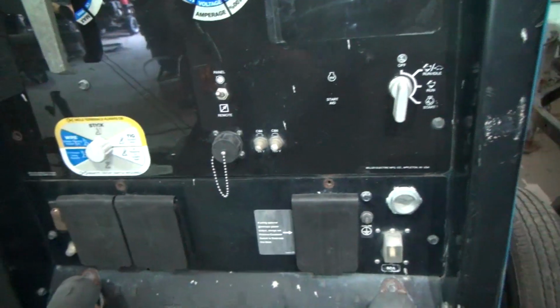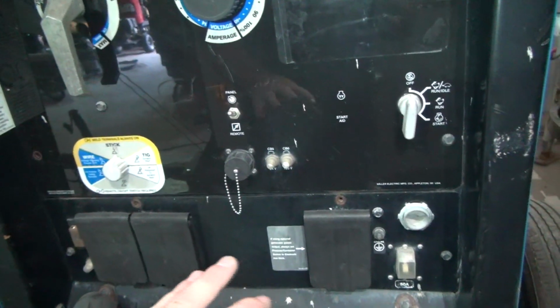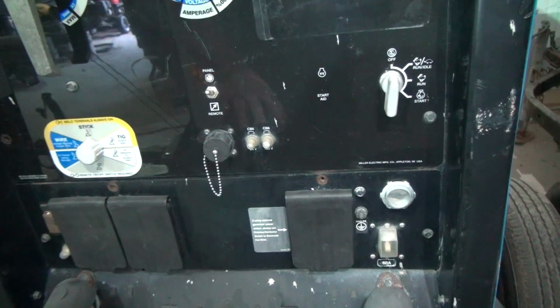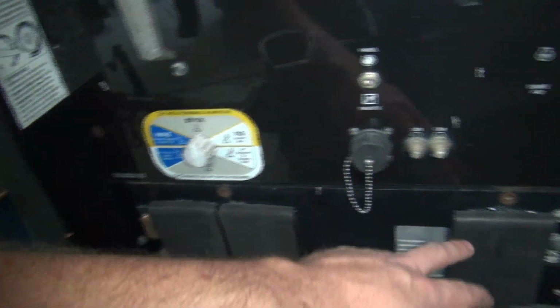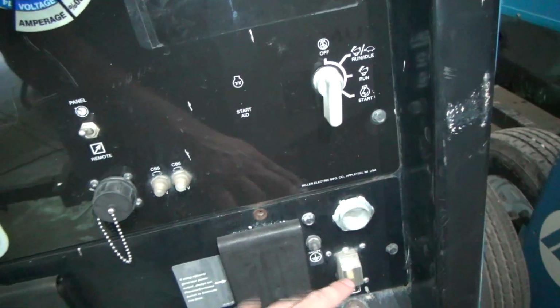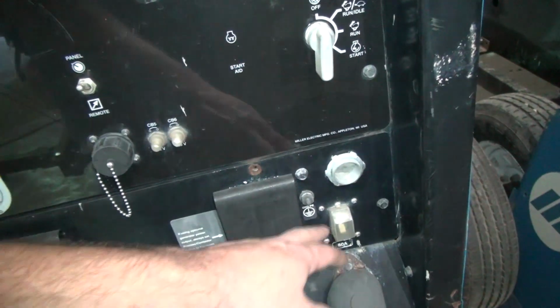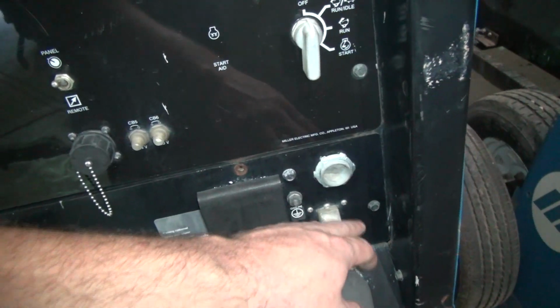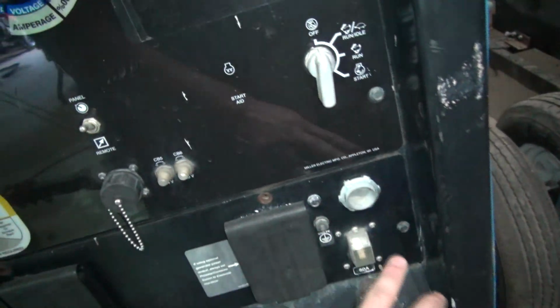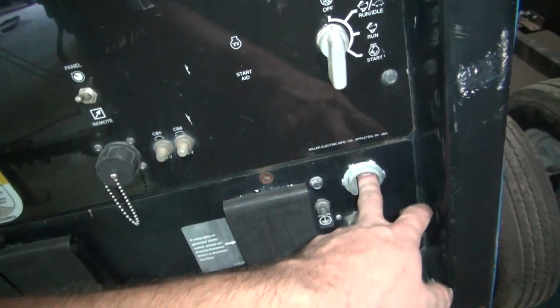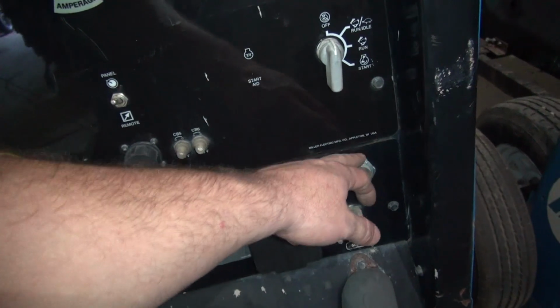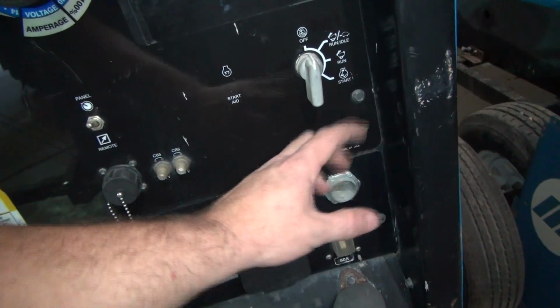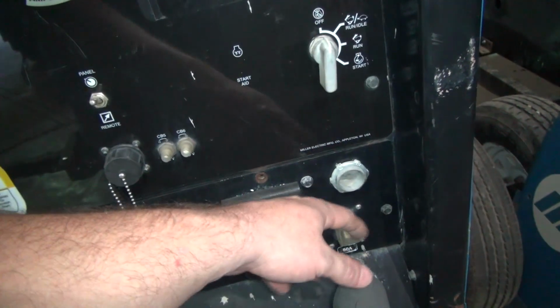These machines have what Miller calls the 3-phase power option. If you take this panel out—there are supposed to be 4 screws, though 2 are missing—the panel folds forward, and behind the breaker there are lugs you can hardwire into. You feed a cord through here, and there's a cable clamp behind it to hold it secure and keep it from being pulled out.